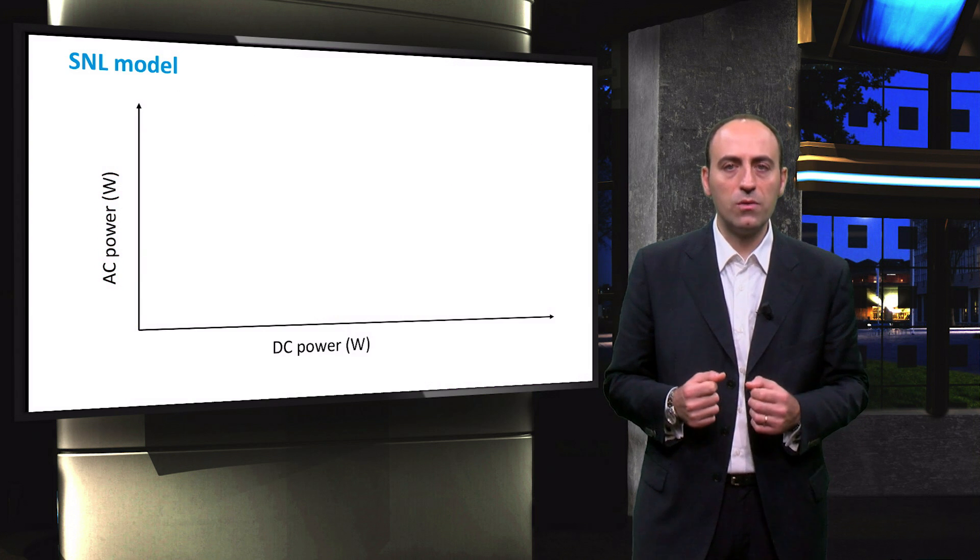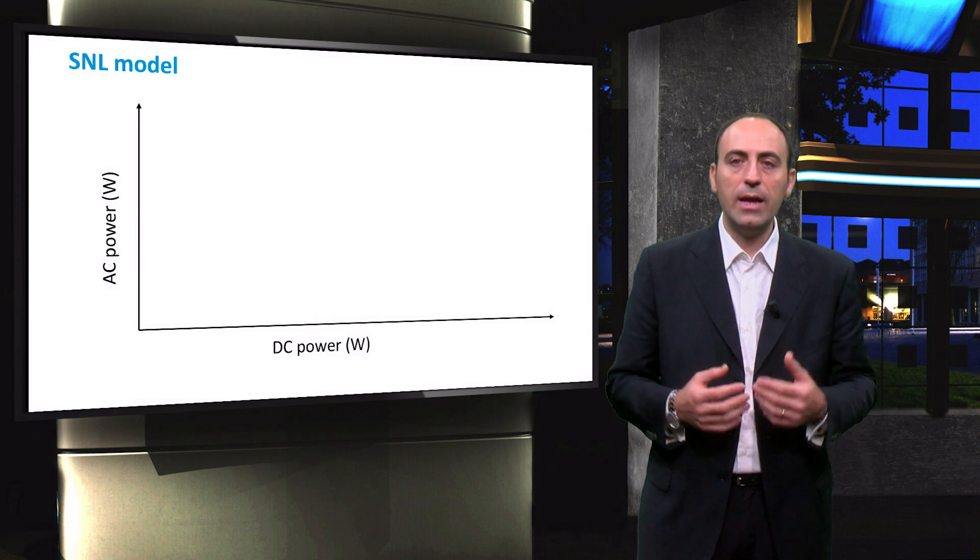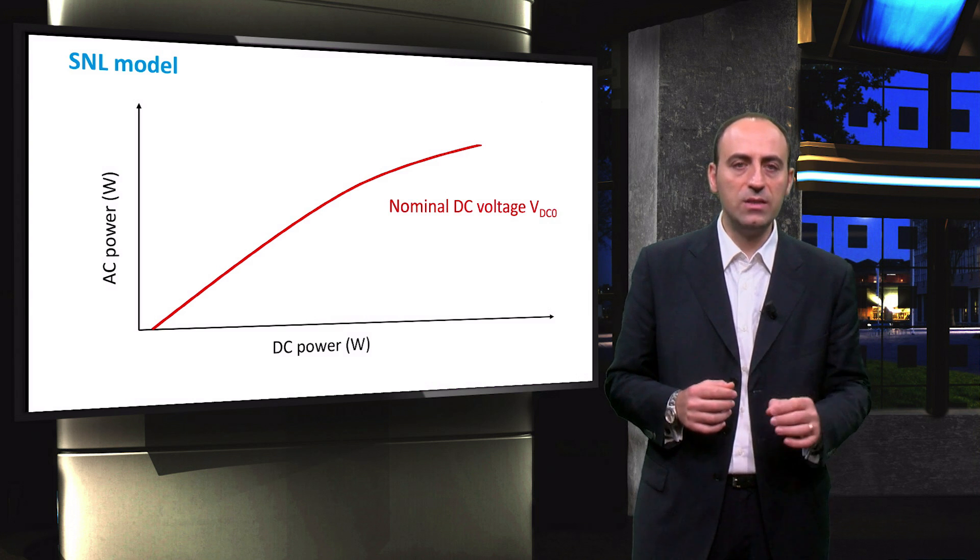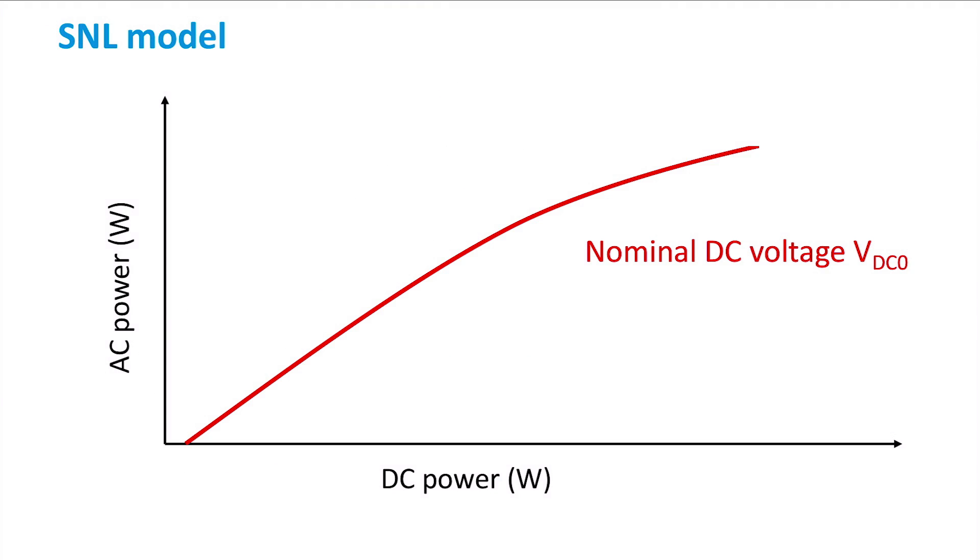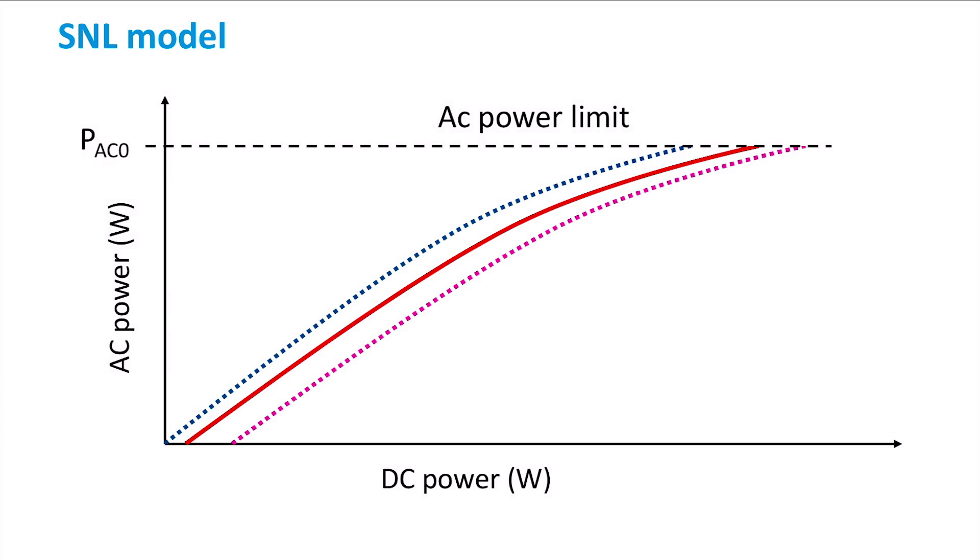With the Sandia National Laboratories model, it is possible to define some parameters that help describe the efficiency of the inverter. Let's consider a device working at nominal voltage VDC0. It is possible to notice that the pattern changes whether we work with a lower or a higher voltage. It is important to underline that in the diagram shown, the non-linearity of the input-output behavior of the inverter is emphasized. The AC power limit for which the inverter is designed is PAC0 and provides the nominal DC power PDC0 when it crosses the nominal voltage line. The curvature C0 is the parameter used to describe the non-linear nature of the inverter characteristic.